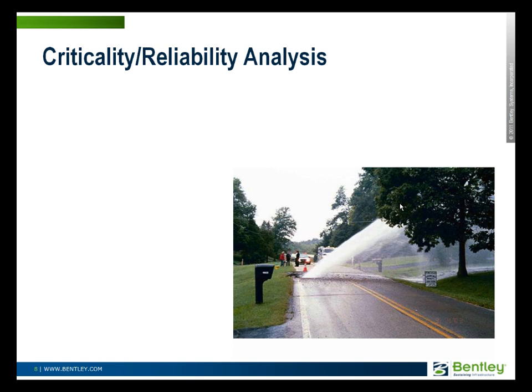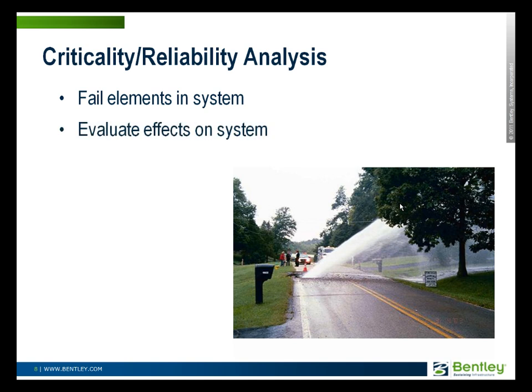You also want to look at what happens when pipes break and the system has to be shut down. This is called criticality analysis or reliability analysis, where you're failing elements in the system hydraulically in the model rather than out in the real world — because you don't want to be shutting off pump stations or closing off pipes just to see what happens. You'd rather do this in a simulation model and see what the effect on the distribution system is. Which customers are going to be put out of water or have their pressure adversely affected? This may lead you to put in more piping or better valving to isolate problems to a smaller area. Valves are very important: a single pipe break can be a minor nuisance affecting a couple of customers, or it can knock out the entire distribution system depending on where the valves are located.